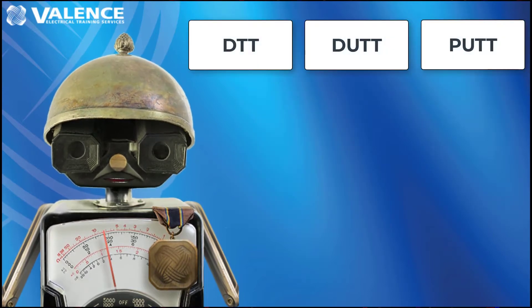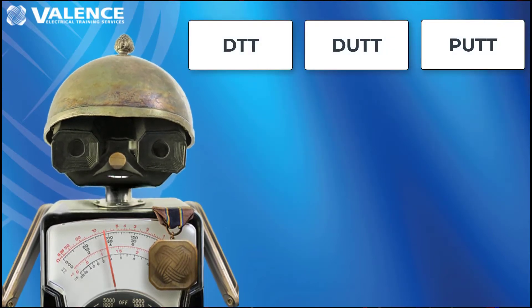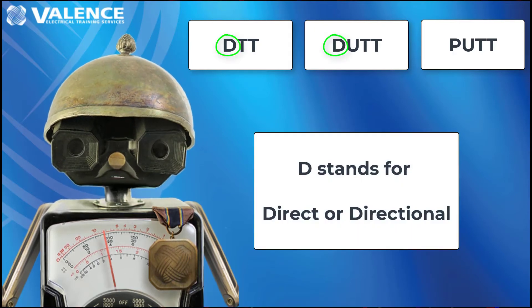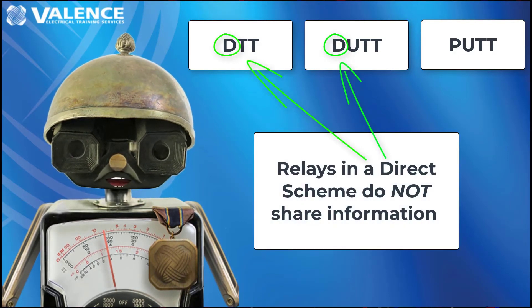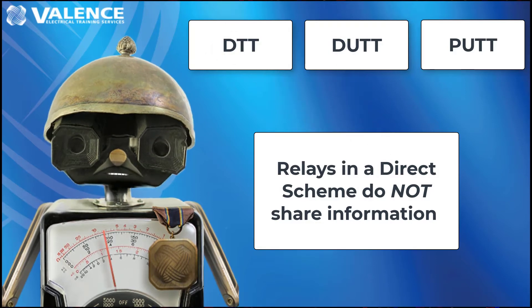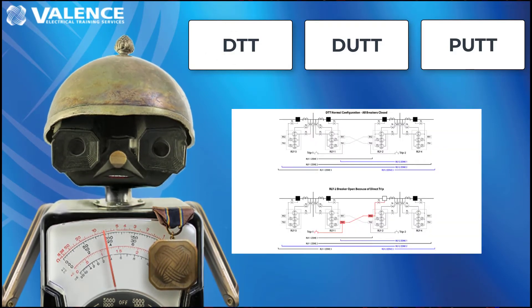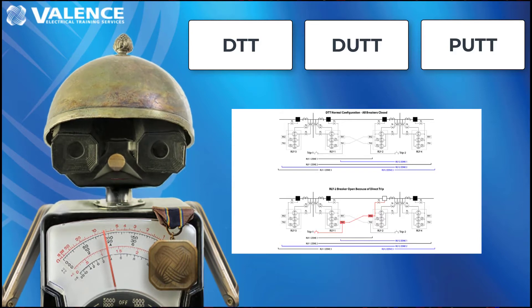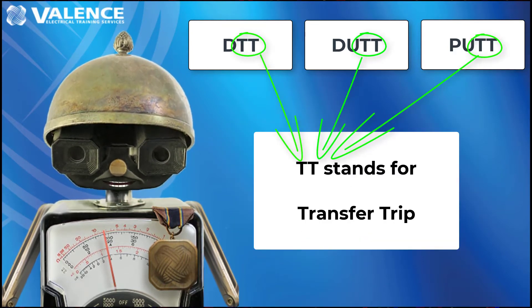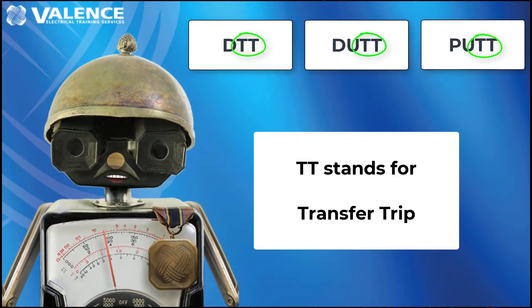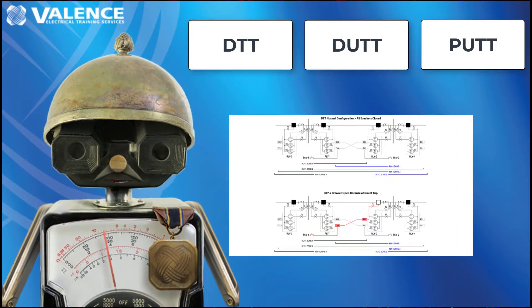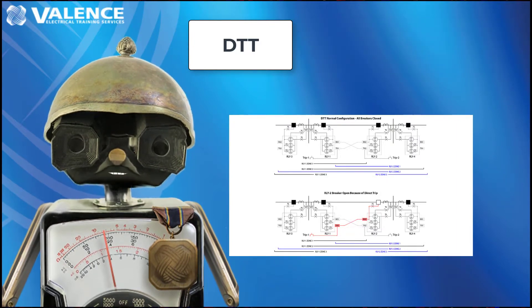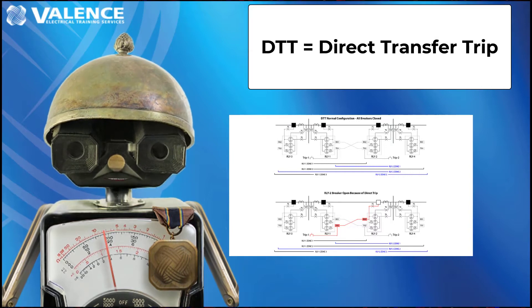These acronyms can be confusing, so let's break down the code to help you figure out what they mean. If the scheme starts with the letter D, the D can stand for direct or directional. Relays that do not share information back and forth are in a direct scheme — one relay simply tells the other relay to trip and the other relay follows the command. The TT at the end of the acronym stands for transfer trip, meaning that a remote relay is sending a trip signal to the other side. If I told you we were going to test a DTT scheme, you could translate the acronym to mean direct transfer trip.